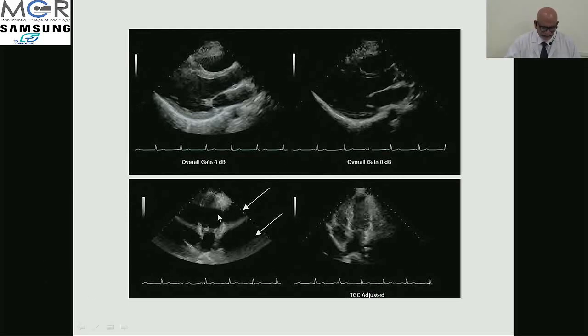Now here the frequencies coming from the mid portion of the ventricle are not properly seen. So here you can use time gain compensation, where the frequencies from this portion can be enhanced, so the picture looks uniform. Use this according to the need, or you can reduce it. The idea of time gain compensation is that the frequencies coming from the near portion of the probe are much stronger than those coming from far from the probe. So you have to suppress the near frequencies and increase the far ones for uniform image quality.